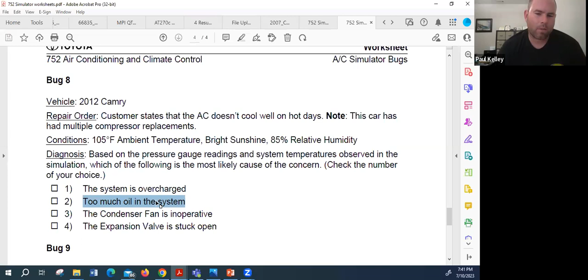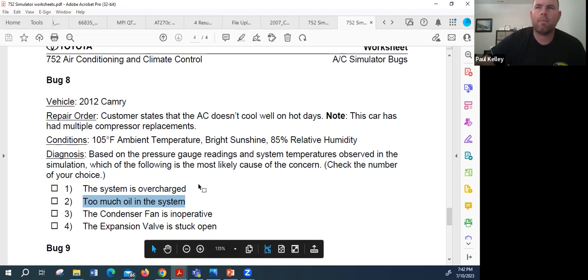Multiple compressors have been replaced. The customer has been putting compressors in, and each time one shows up, it's probably already full of oil. So we put a new compressor in, charge another 2 ounces of oil, then another full one goes in, and it's hard to get the oil out of there. So this one's just been collecting oil for us this whole time.